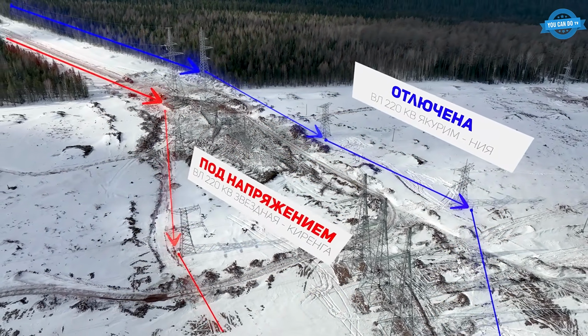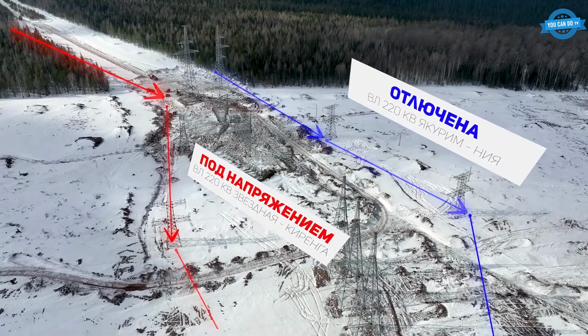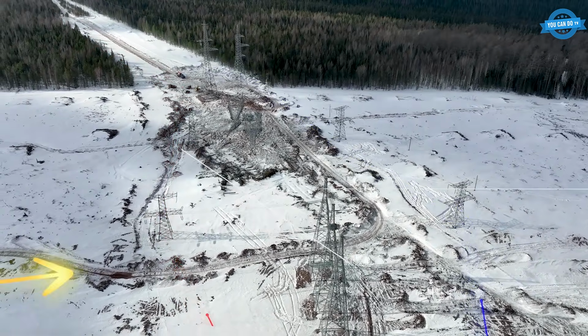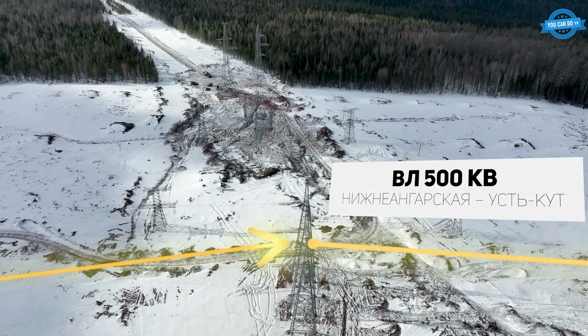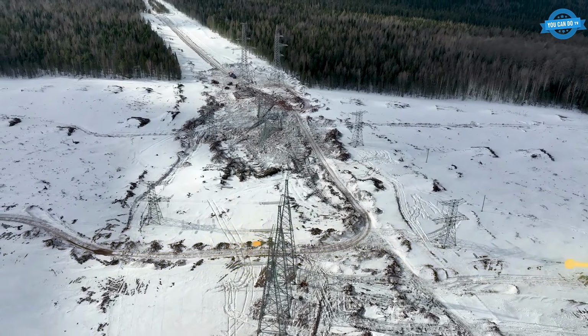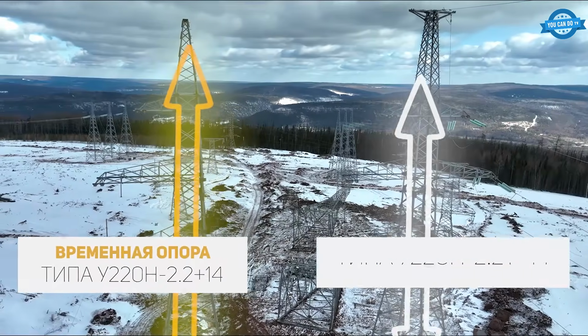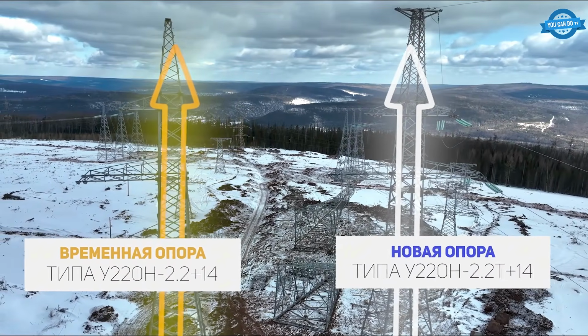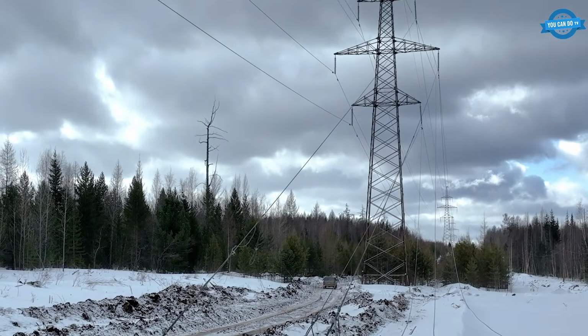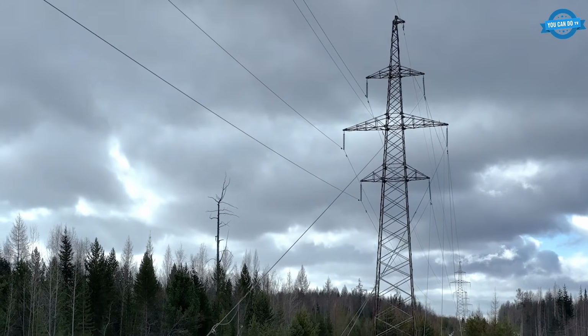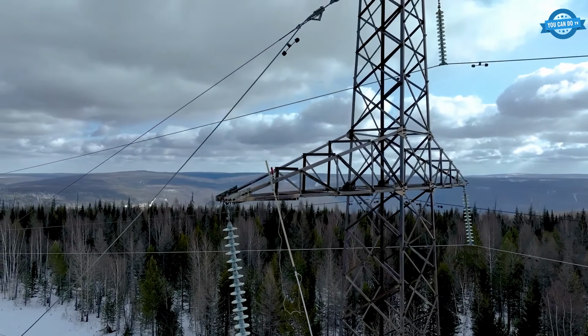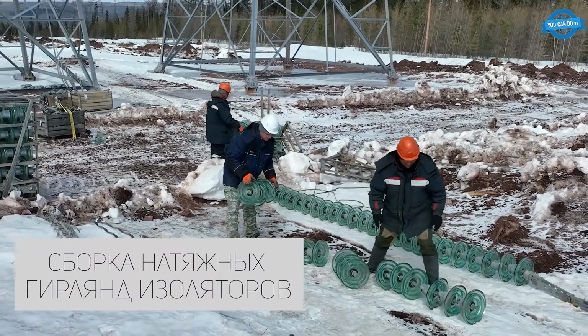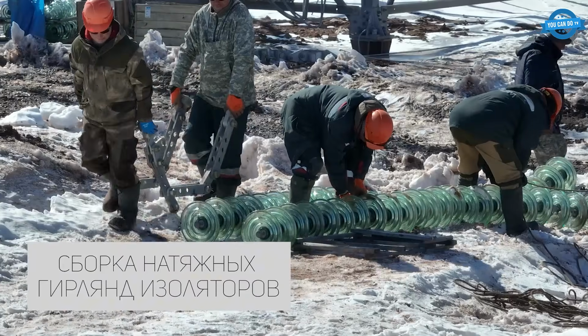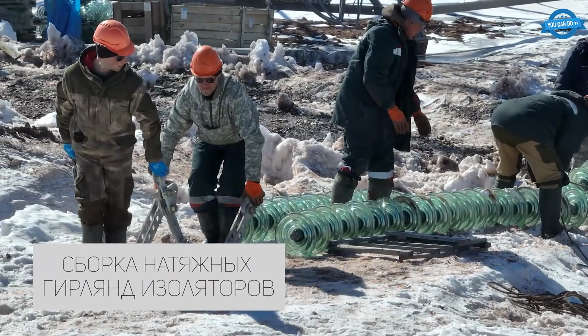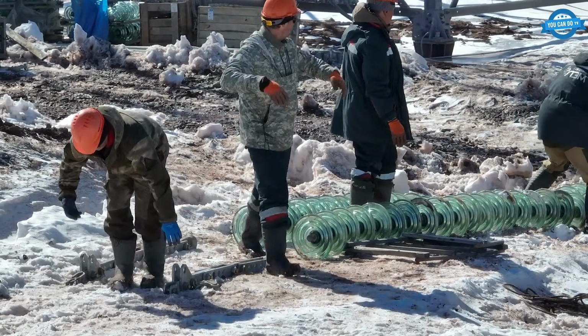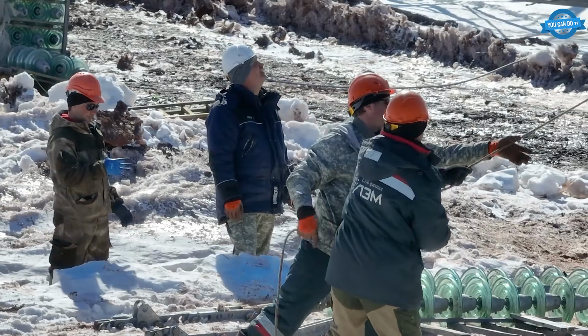Cross one transmission line over another and the schedule becomes the enemy. The lower line has to be switched off, dismantled, rebuilt, and re-energized in 6 days flat, while a brand new 500 kilovolt span gets strung above it. A reconstruction at the crossing of an active 220 kilovolt line with a new 500 kilovolt route runs to a 6-day shutdown.